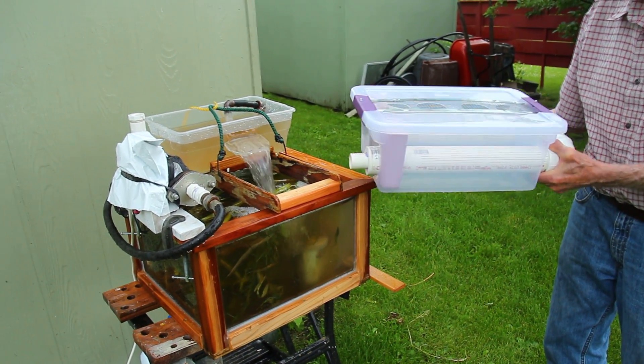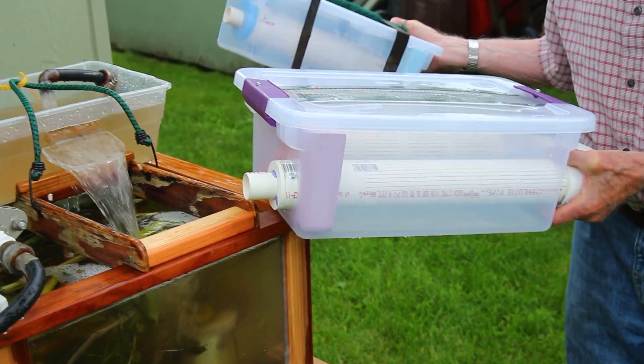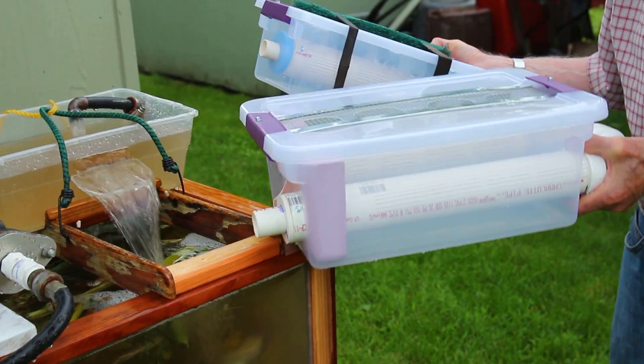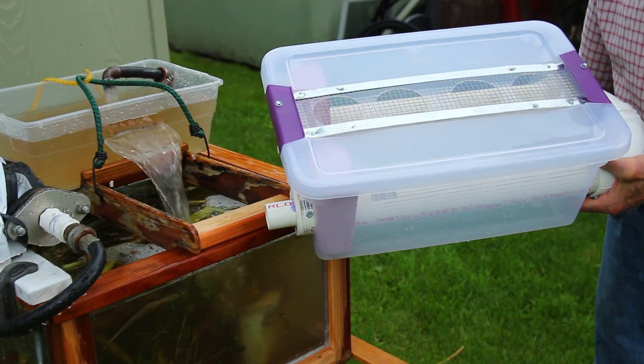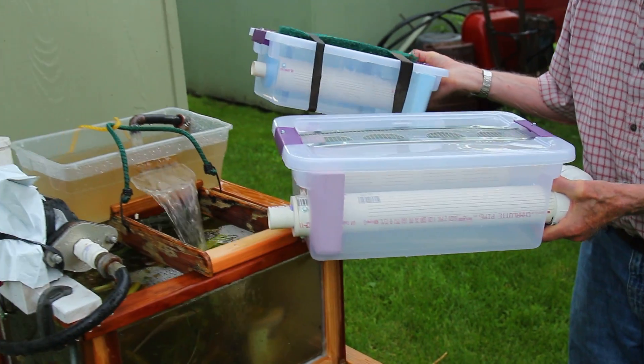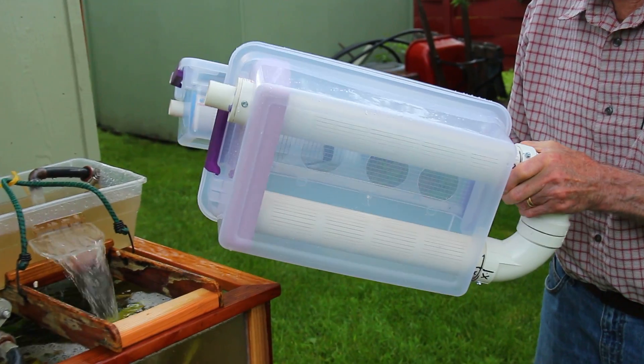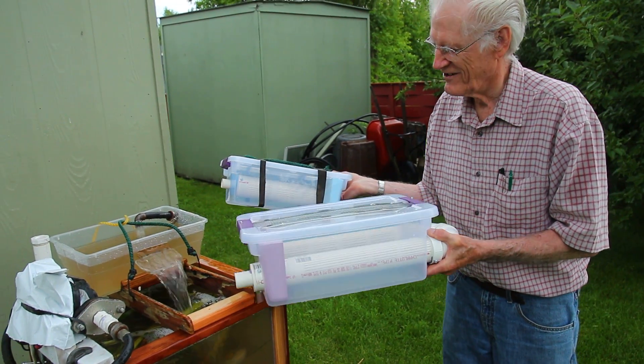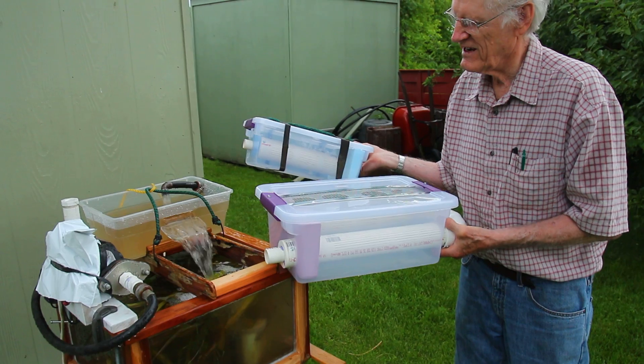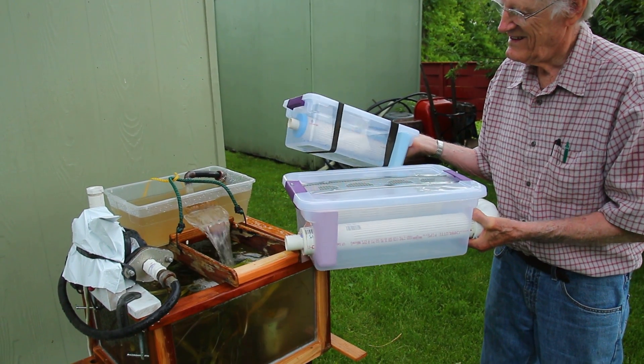What about that filter itself with the grooves in it — what diameter is that? That's two-inch pipe, and there's a double in here. This single will handle 10 to 15 gallons per minute, and the double will handle about 30 gallons per minute.